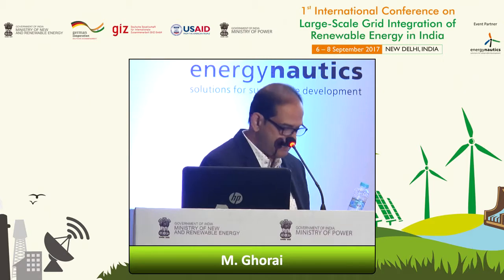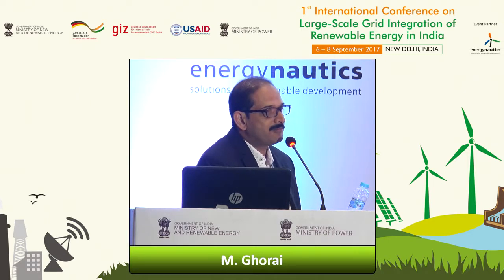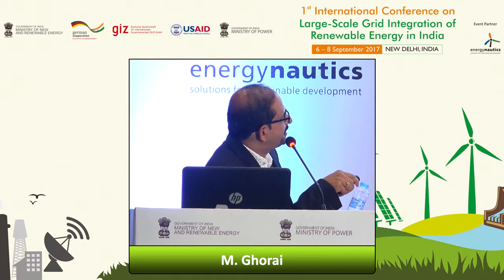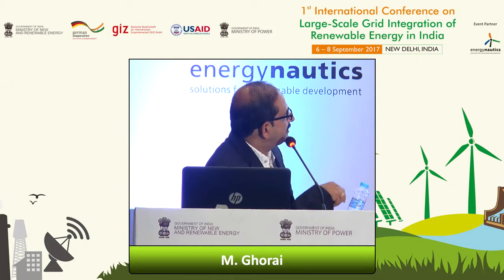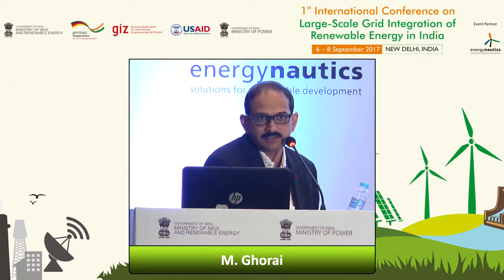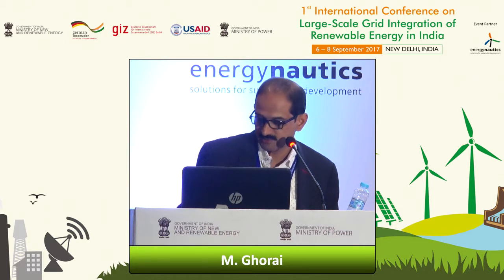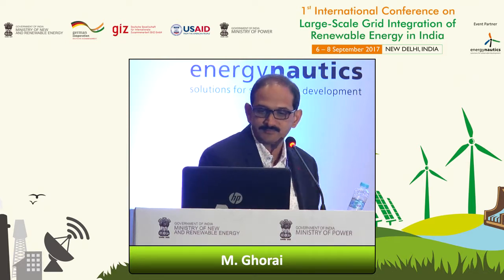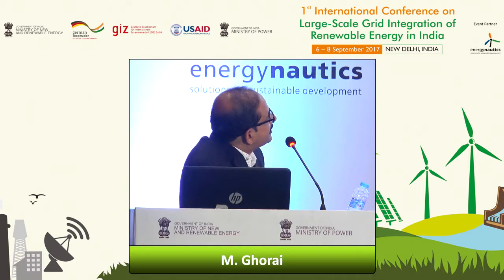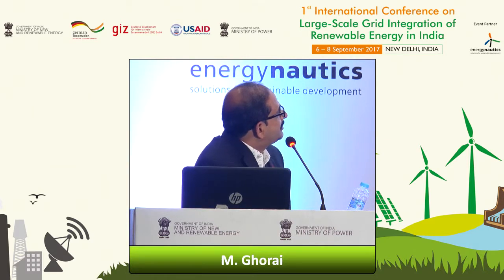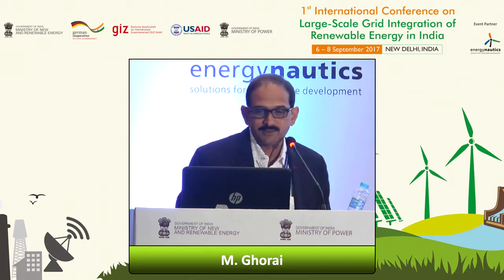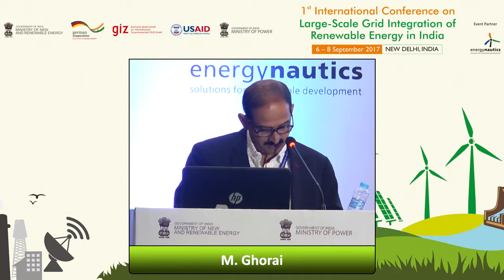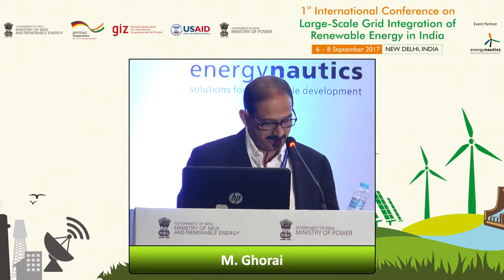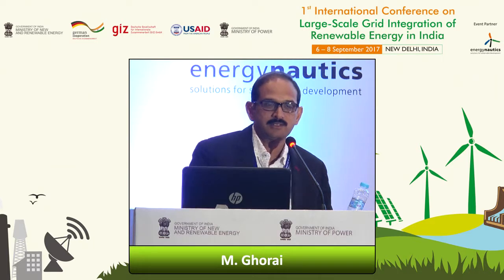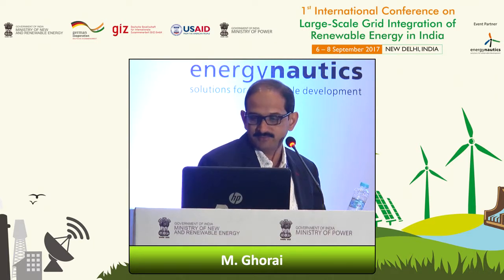So going forward, I think many of the wind farms, or few of the wind farms, would be requiring a STATCOM and reactor bank or capacitor banks, and also control through these sophisticated controls. And similarly, what I showed earlier, meeting the reactive power capability, similar to the earlier graphs. So this is what it is going to look like, in my opinion, if the grid code is approved the way it is already written and being reviewed.